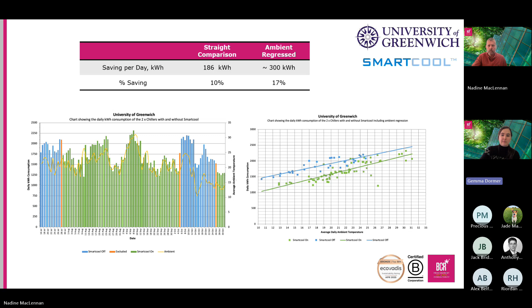What the unit actually does is fairly straightforward - it monitors continuously and adjusts the compressor within the HVAC, heat pump, or refrigeration system, so that the cut-out and cut-in points run at more efficient pressures. In simple terms, each time the compressor runs, it delivers the cooling more effectively, so it doesn't need to run as long to achieve the same temperature.